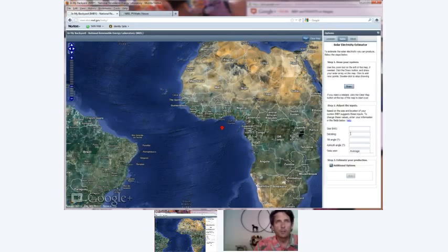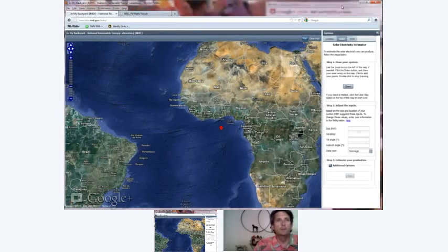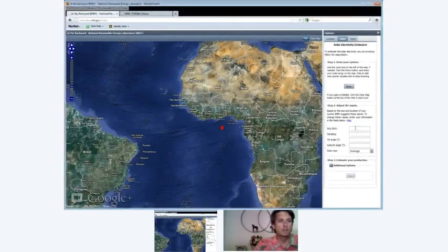You go to solar, and there's a nice menu to work with on size, and you can put in 4 kilowatts. Derating is typically 0.77. Tilt angle, 39 degrees for that particular location. Azimuth means how far south or north. And of course, this is completely a south-facing roof, so you can say 0. And once you fill in all those, a run button is supposed to come up.